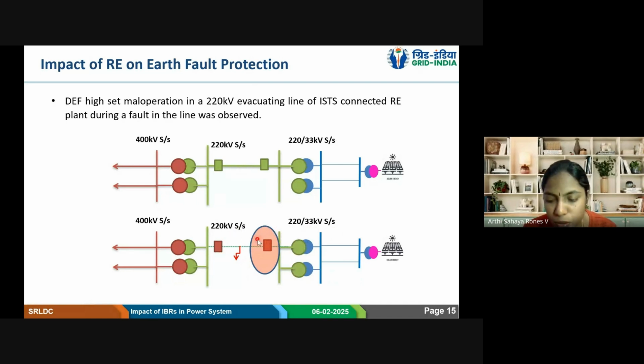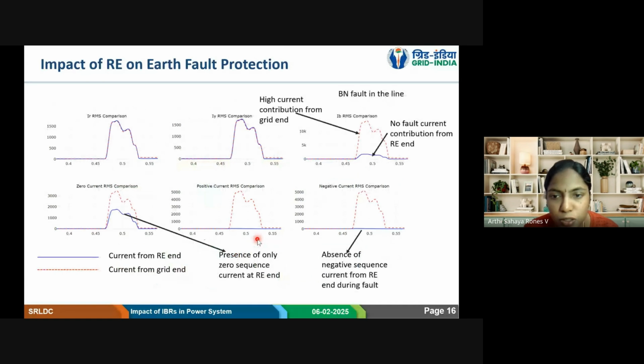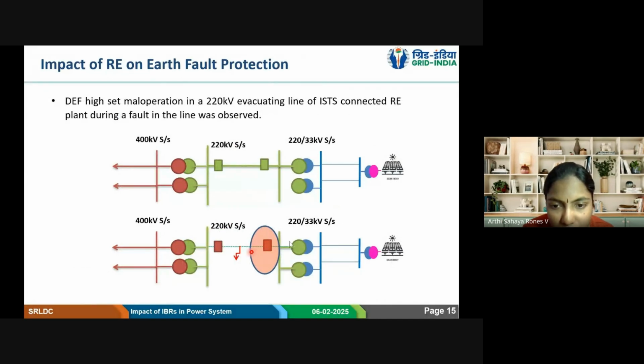In this particular DR, instead of showing it in the DR format, I have plotted it in Python so that we can understand the difference. I'll try to explain from here. The blue solid line is the current from the RE end, and the red dotted lines are the current from the grid end. First let us see the grid contribution. During the normal condition, there was no RE generation, so it's almost 0. All of this is IR RMS, IY RMS and IB RMS of both grid and RE end currents shown. Down here we are seeing zero sequence RMS, and then positive sequence and negative sequence current of both grid and RE end. That is this current and this current, both we are seeing now.